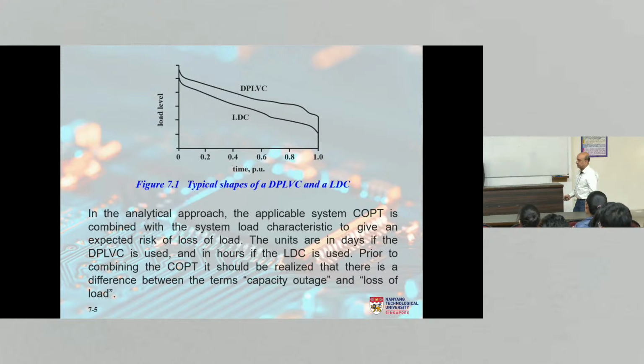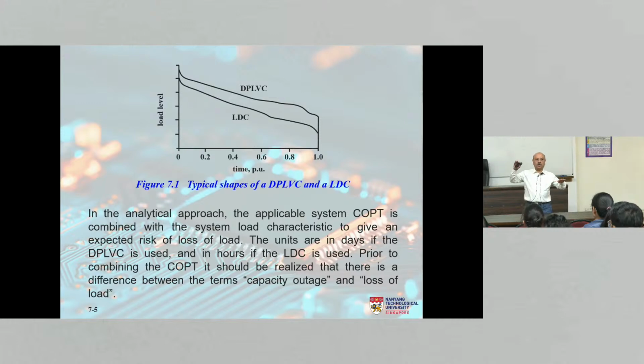So you will see through calculations, it's not that hard at all. But before we use the COPT, you must realize that there is a difference between the terms capacity outage and loss of load. Yesterday I told you that when we develop the capacity outage probability table, we should know what is loss of load, correct? That means whenever the capacity becomes less than the load, after you have considered all kinds of remedial actions, support from interconnections, voltage reductions, voluntary load curtailment, and so on and so forth. And still, if your capacity is less than the load, then you will curtail load, you will cut load. So that situation is loss of load.